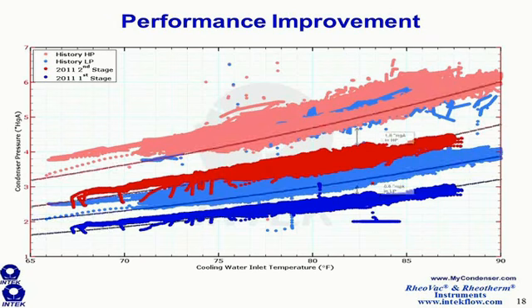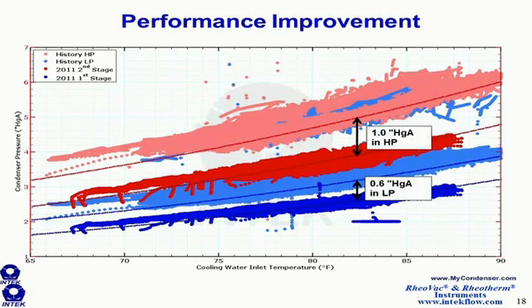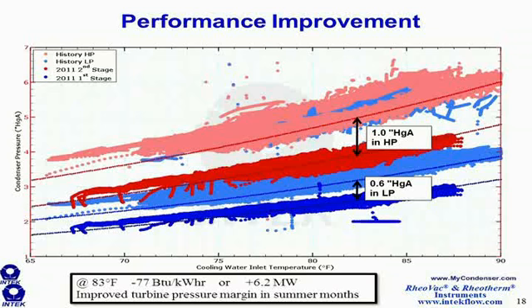You can see a 1-inch pressure decrease in the second stage pressure, a 6/10 decrease in the first stage pressure, and that resulted in an 80 BTU per kilowatt hour heat rate reduction. And in the summer months, when they operated in the heat input limited mode, there was an additional 6 megawatts of generation.